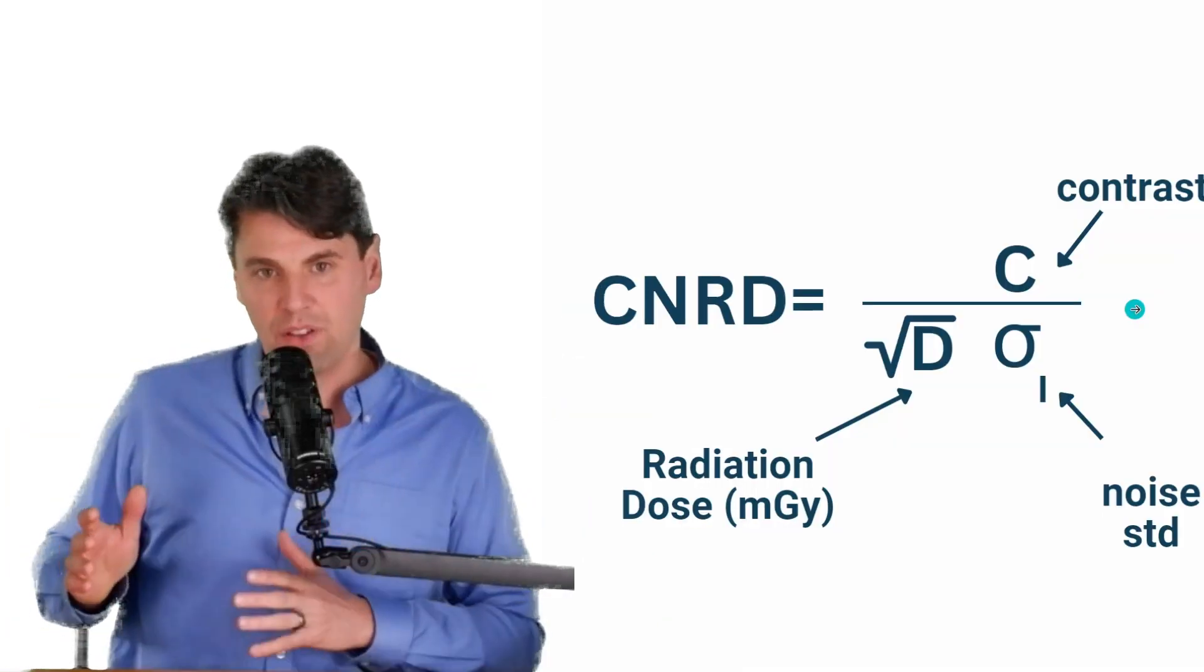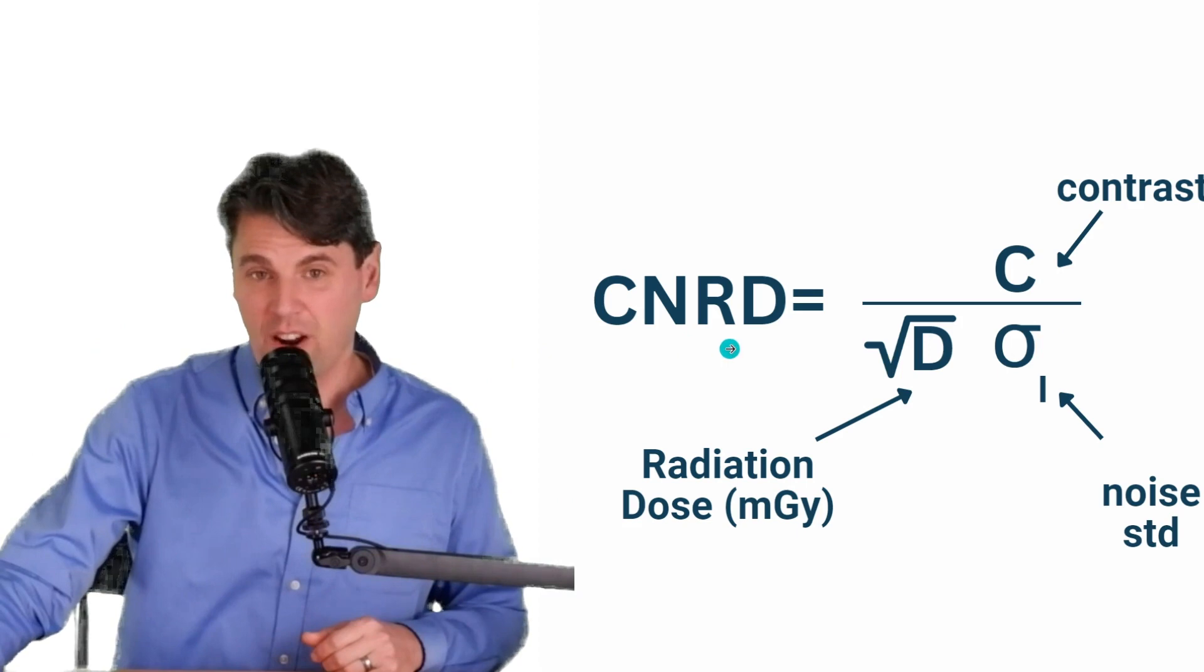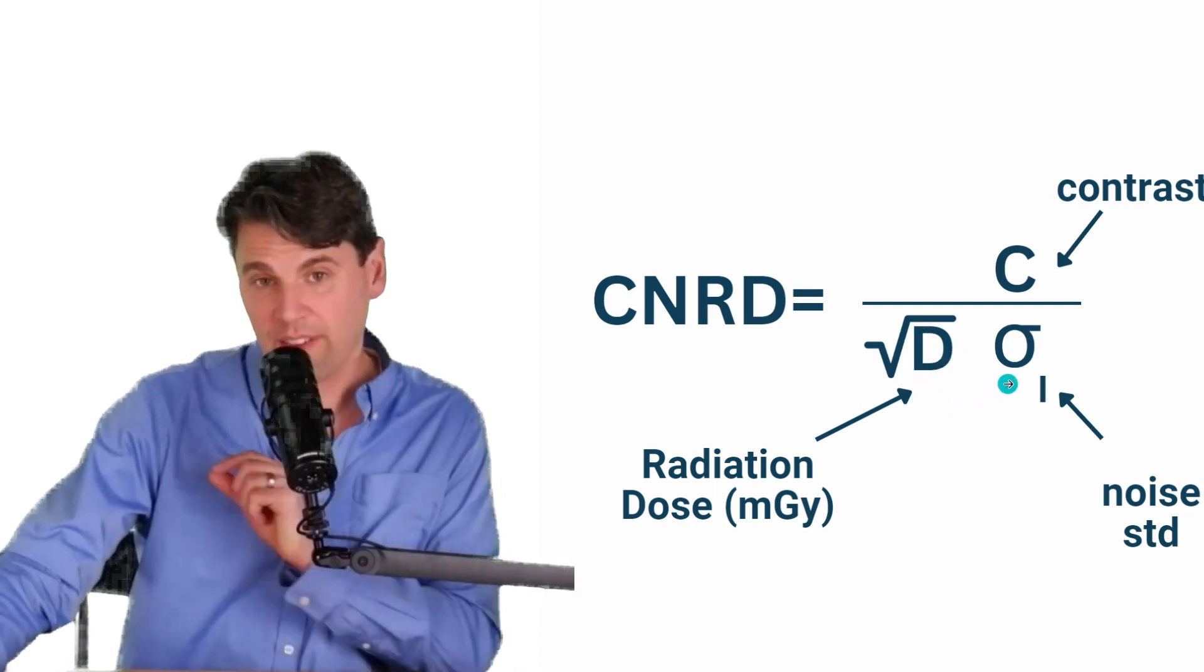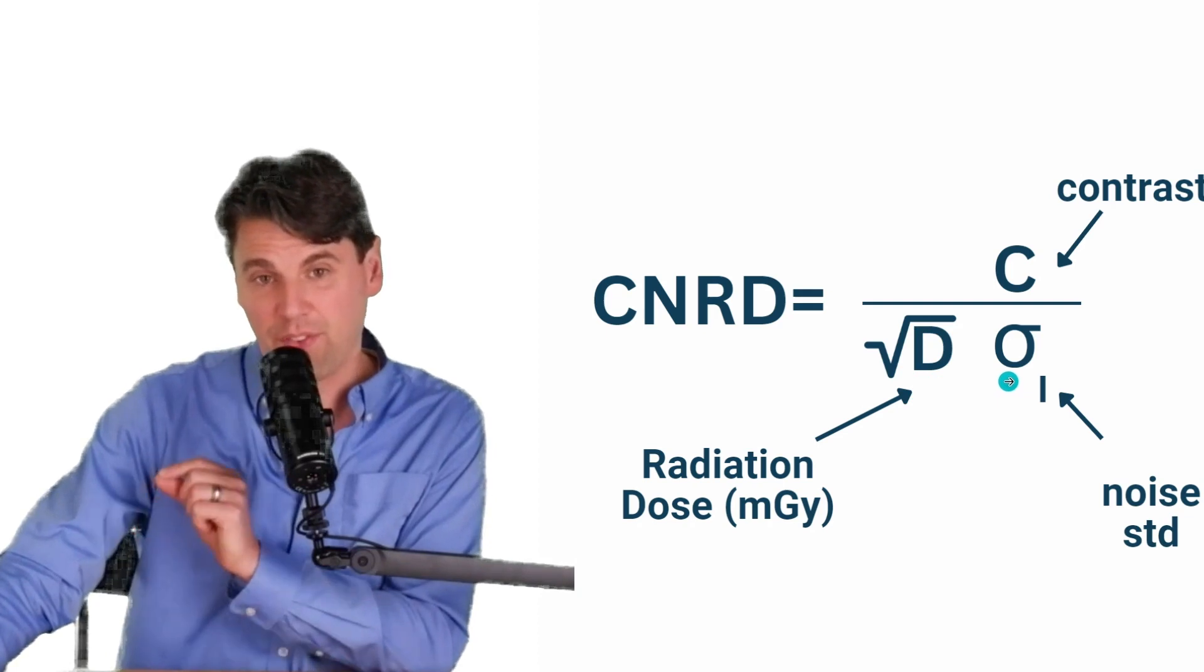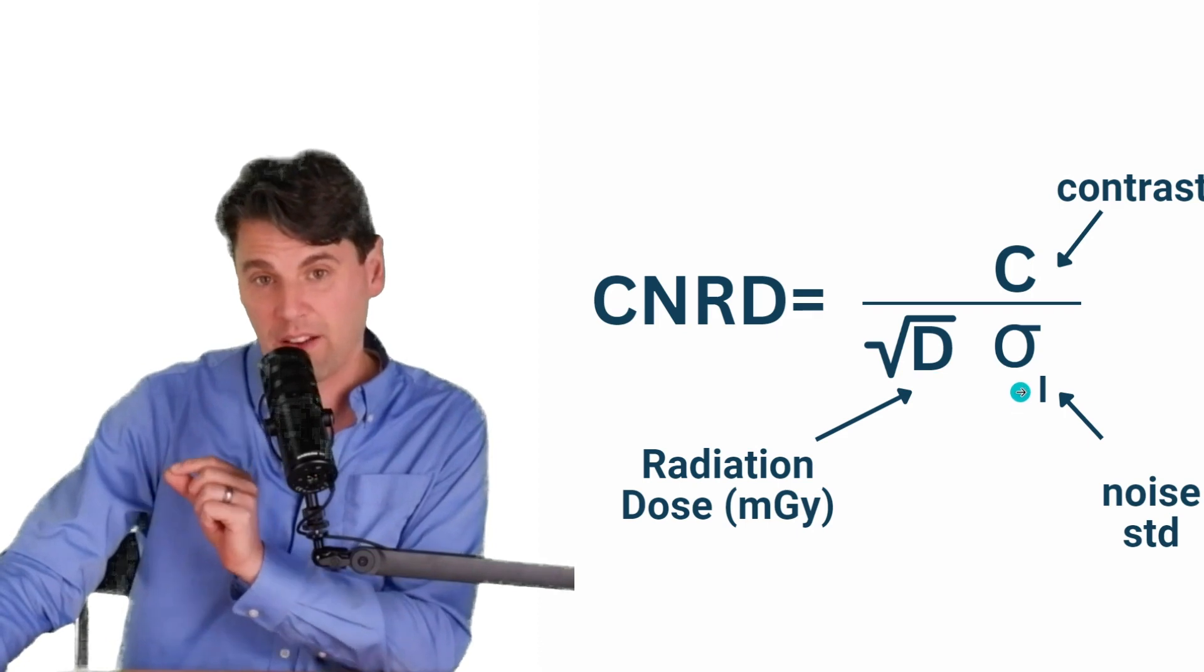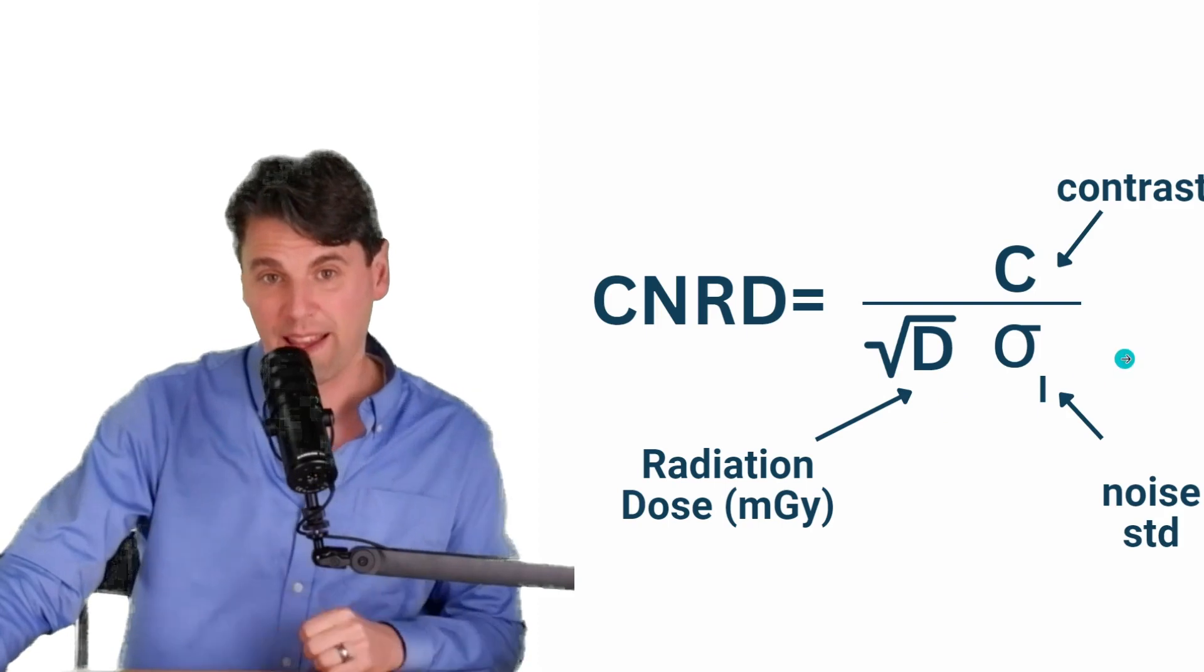The optimization criteria that Willie defined in the first paper on this topic was actually called the CNRD. It's actually the contrast per given noise level. And then we have the square root of the dose in the denominator here. We took the square root of the dose because we have the standard deviation of the noise. And if you remember, that's the relationship here between those two parameters. If we have the standard deviation of the noise, then we need to take the square root of the dose because the dose went as the noise variance.